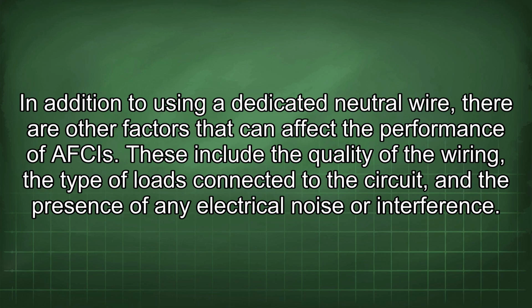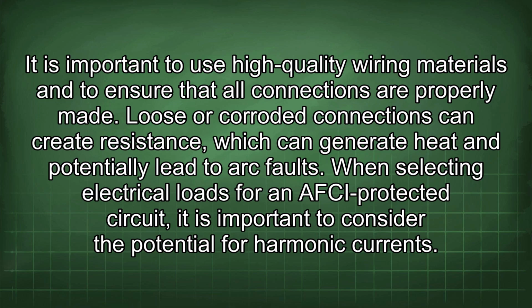In addition to using a dedicated neutral wire, there are other factors that can affect the performance of AFCIs. These include the quality of the wiring, the type of loads connected to the circuit, and the presence of any electrical noise or interference. It is important to use high-quality wiring materials and to ensure that all connections are properly made. Loose or corroded connections can create resistance, which can generate heat and potentially lead to arc faults.